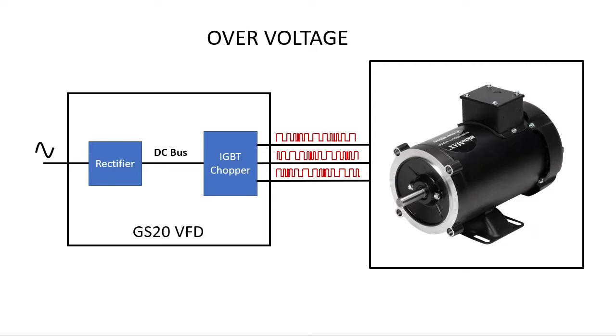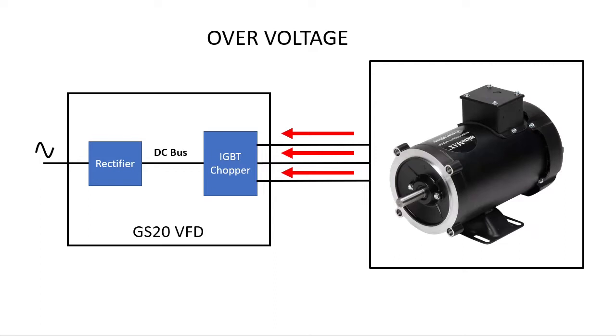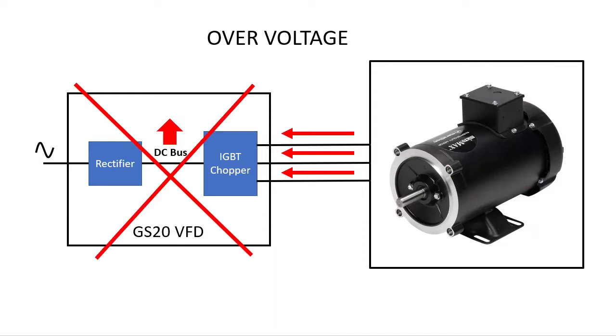So the motor becomes a generator and it pushes current created by the rotating magnetic fields back into the drive. That additional current adds voltage to the internal DC bus which makes the bus voltage increase. The problem is the semiconductors inside the drive can only handle so much voltage and if that voltage gets too high, they burn up and you end up with an expensive paperweight.